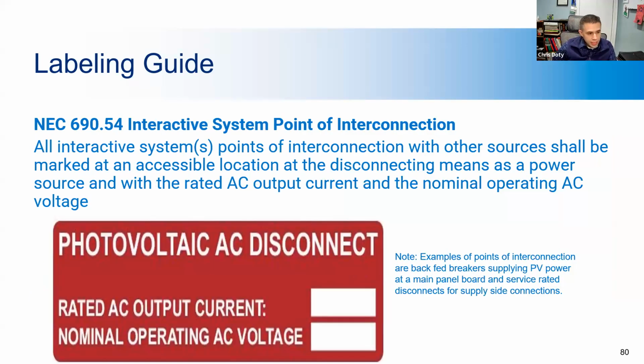Here you have another example of the PV AC disconnect. You need the AC output current and AC operating voltage. We already went through this one. A lot of times these are missing, incomplete, or not suitable for the environment. But there are many manufacturers that make labels that will endure outdoor conditions such as wind, snow, rain, UV degradation, all that stuff. And this is required at the interactive system point of interconnection.